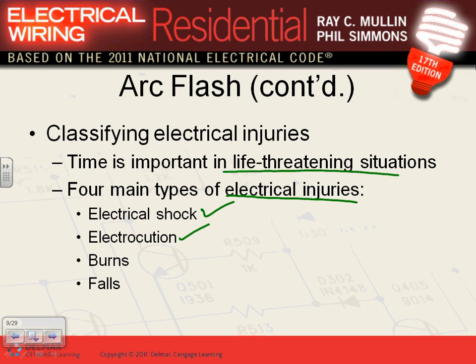So that's basically electrocution, worse than shock. Then there's burns and falls. Arc blast burns are a big deal. If you ever go into remodeling jobs, be very careful. When electricians open a panel, I've seen this many times, if you open a 2000 amp switchboard, move away at least 10 feet, because that big ball of fire can come out. They should be dressed up with PPE when they work on it. If not, and you're the project manager, remind them to put on PPE when opening these panels. The burns come from a big ball of fire from the arc. If you search YouTube for arc flash, you'll see tons of pictures of burns.